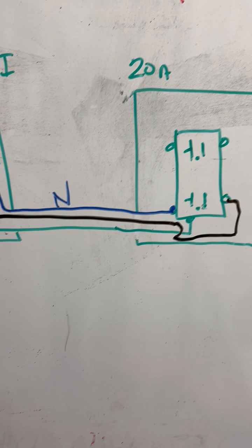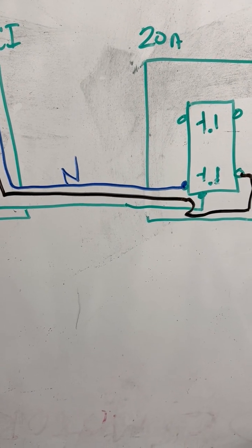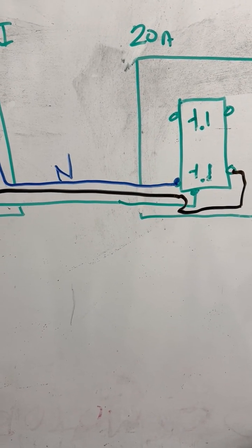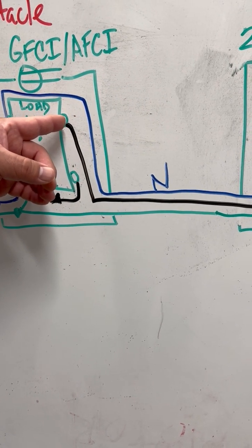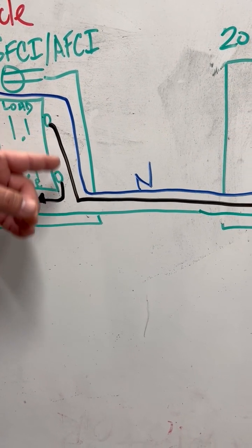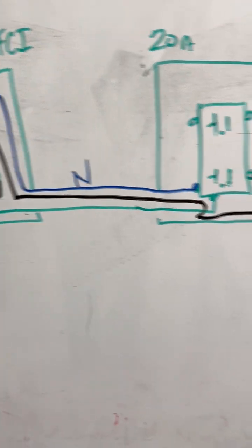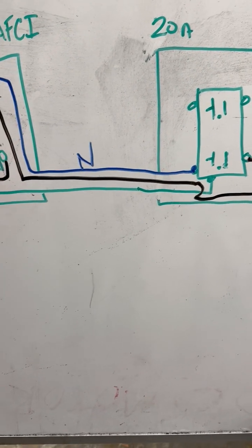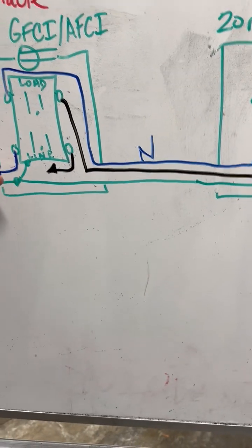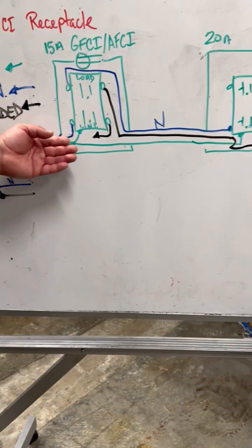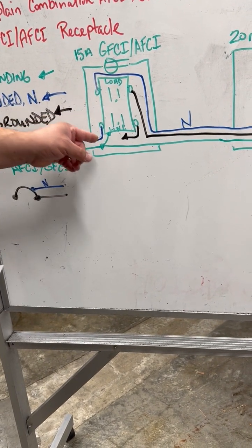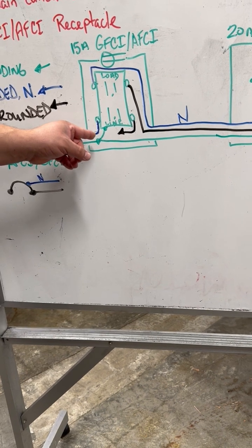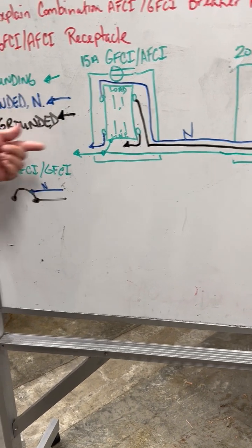receptacles. We also have the ungrounded conductor coming in from the home run, coming in on the line side, exiting out through our load side, continuing on to the downstream receptacles. But one of the things that I point out to them is that incoming conductor comes in, I'm gonna utilize that knockout primarily. Why? Because it's closest to my grounding raised nipple. It's coming from this direction.